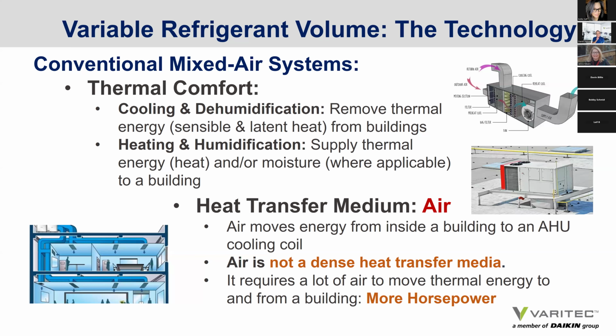Well, to maintain thermal comfort, HVAC systems cool and dehumidify buildings by fundamentally moving energy. That's what we do in the mechanical industry. We are energy movers. We move sensible and latent energy. In heating mode, we actually add energy to a building that is being lost through the perimeter walls to colder ambient conditions. Conventional HVAC systems accomplish this by using air as a heat transfer medium. We flood the building with a lot of air to capture the energy gain in the building and to take it back to an air handler where we remove that energy through a cooling coil or add energy through a heating coil to maintain building space conditions. The problem is that air is not a very dense heat transfer medium. So it requires a lot of air to move the energy necessary to condition a building, which means horsepower.